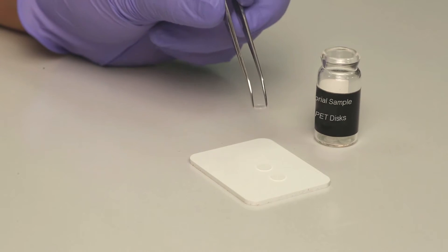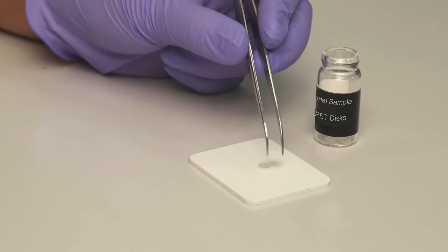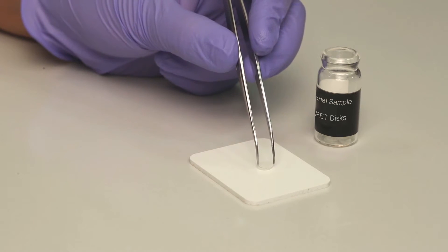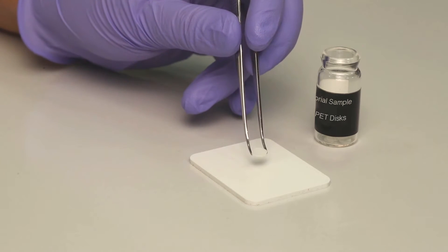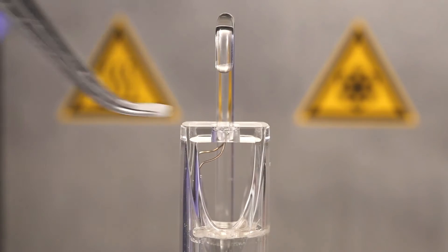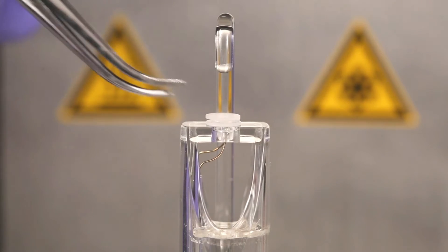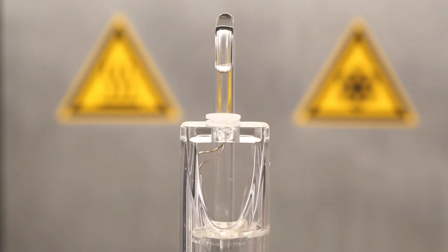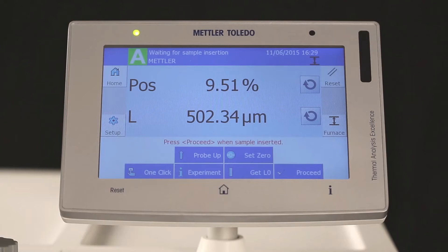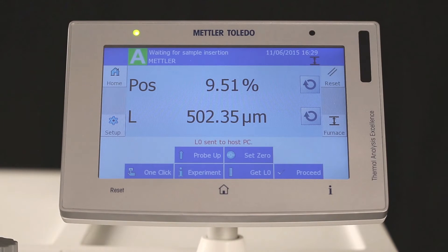Now insert the PET sample between the two fused silica discs and press Set Zero. The initial length is sent to STARe software.